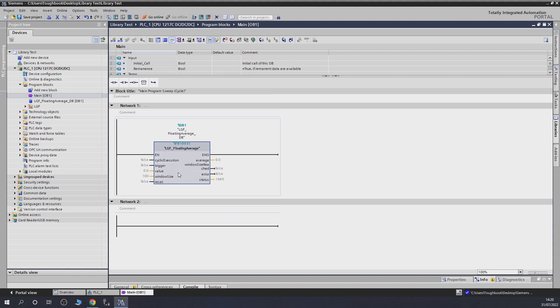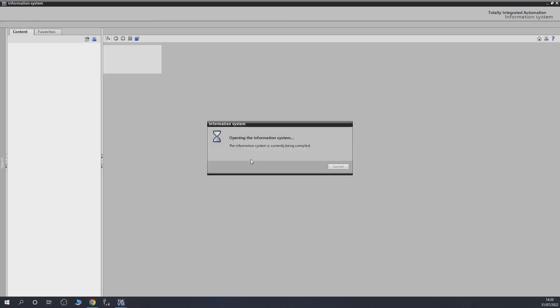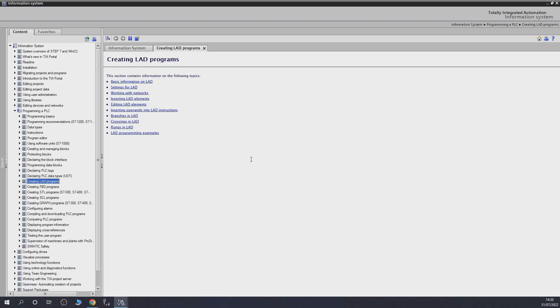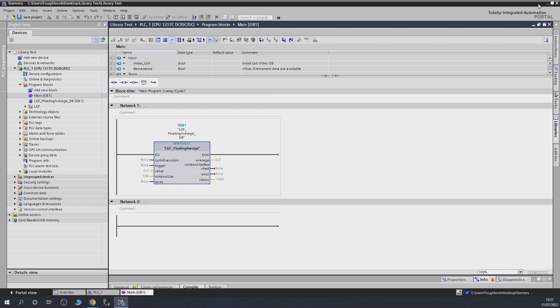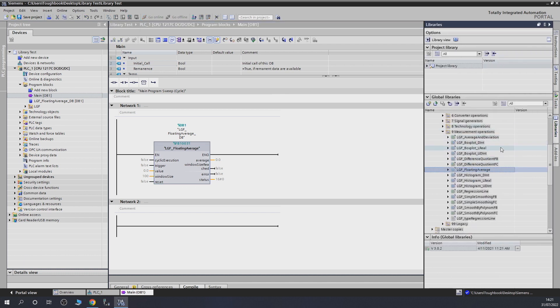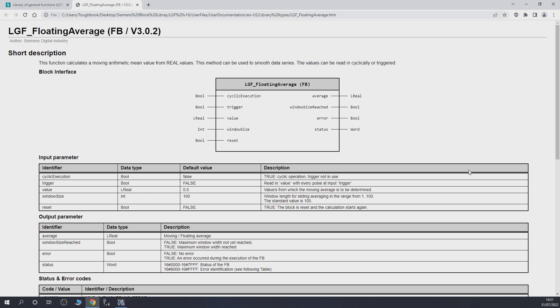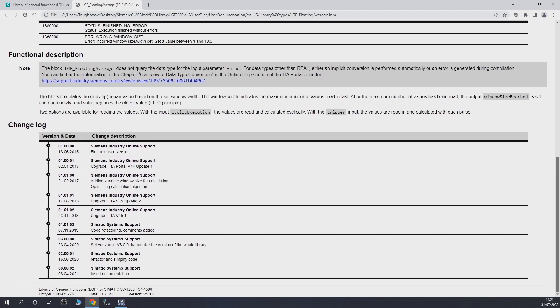If you want to read up on what this function block does and how it works, pressing F1 alone doesn't work properly — it opens a library window that's no good to us. What you need to do instead is go into the libraries panel, select the block you want to work with — say the floating average — then hold Shift and press F1. That will take you to an actual webpage with a full explanation of what the function block does, with full-blown detail. Very useful.